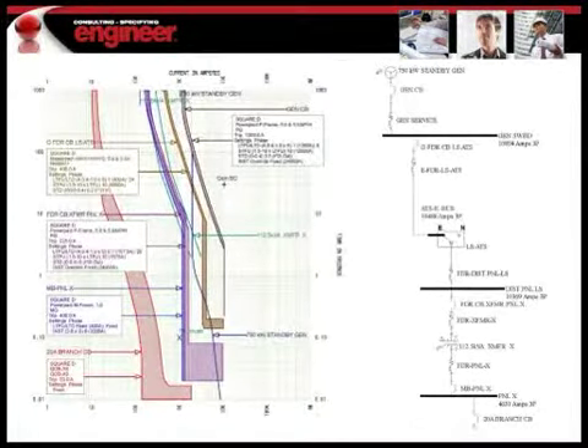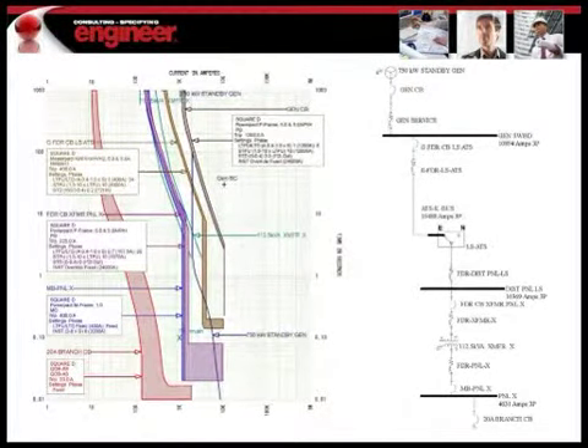As we move forward and look at our emergency side of the circuit, consider when the circuit is served from the single generator. This set of curves demonstrates that our circuit is selectively coordinated when served with the generator. The generator itself produces a lot less fault current than the utility does. And so here you see this set of curves indicates that the system is coordinated. As Jim pointed out earlier, we had to make sure that our generator curves, our circuit breakers fell to the left of the damage curve of the generator, and it does as shown in this diagram.